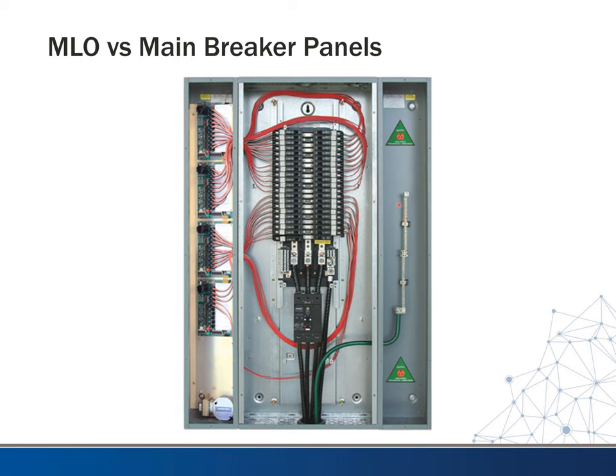And then you see here they have another gutter where for some reason they've brought their ground over here, so they'll be making their ground connections here. This is usually done if they have like an isolated ground, they will do that sometimes. So this is a pretty good example of some different attributes you might see with a panel. And then here are your branch circuit breakers. It's usually like single pole 20 amps or whatever you need there. And then you also have your neutral connection coming in right there.